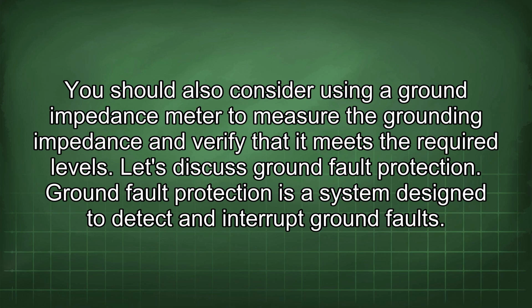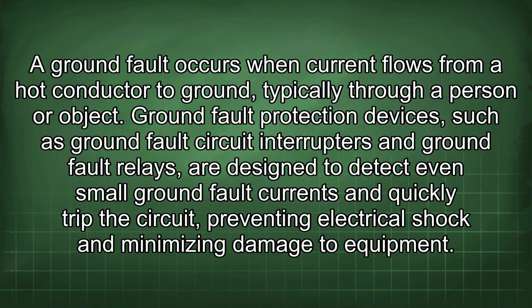Let's discuss ground fault protection. Ground fault protection is a system designed to detect and interrupt ground faults. A ground fault occurs when current flows from a hot conductor to ground, typically through a person or object. Ground fault protection devices, such as ground fault circuit interrupters and ground fault relays, are designed to detect even small ground fault currents and quickly trip the circuit, preventing electrical shock and minimizing damage to equipment.